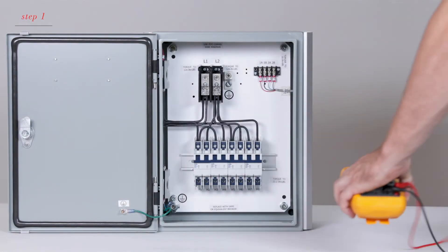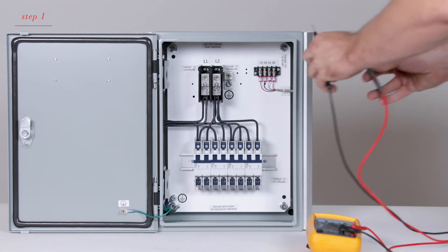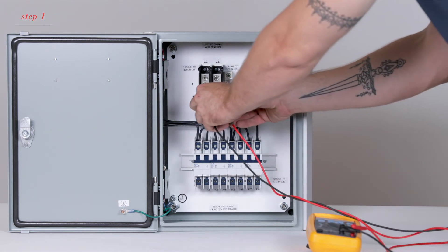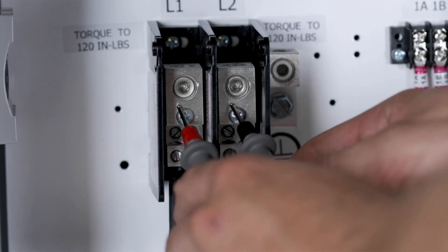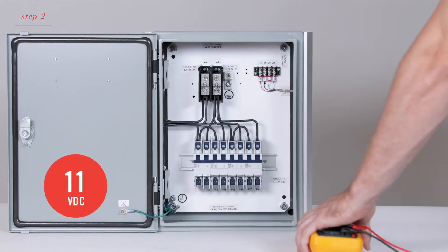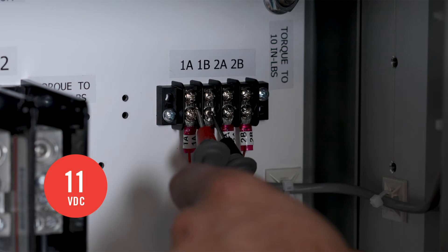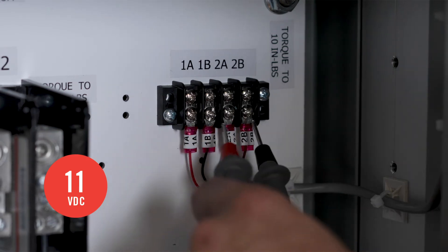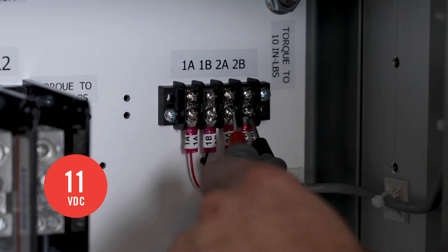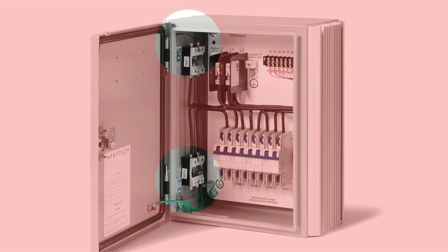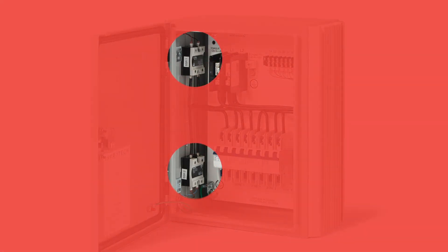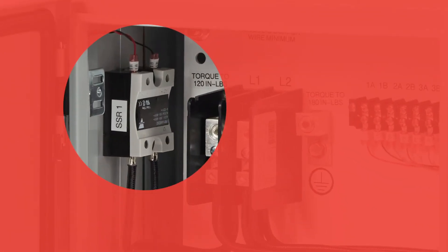First, check to see if there is main feed AC voltage at the distribution block. Next, is the 11 volt DC control signal present between XA and XB? Please note that the X represents the solid state relay number associated with the terminals. You should see a green indicator light on each active relay.